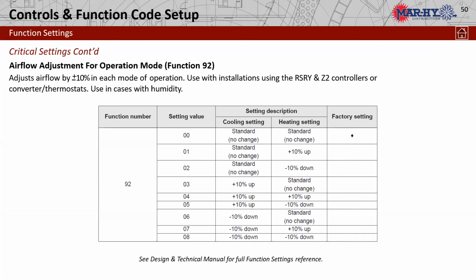This would be in applications where you might have extended run lengths, extended ductwork, and you may need a little more air on the cooling side, maybe not so much on the heating side, or you can even decrease it if need be, and these are plus or minus 10% on each mode. There again, you'd have to look at this chart and see what was applicable for what you're trying to do.